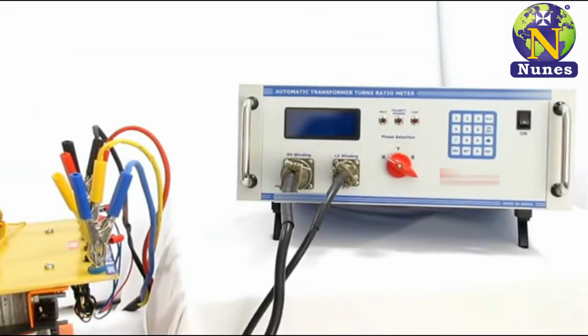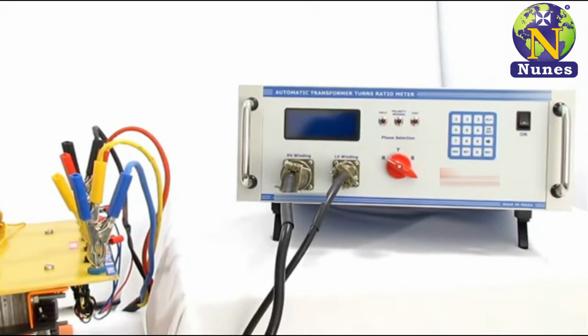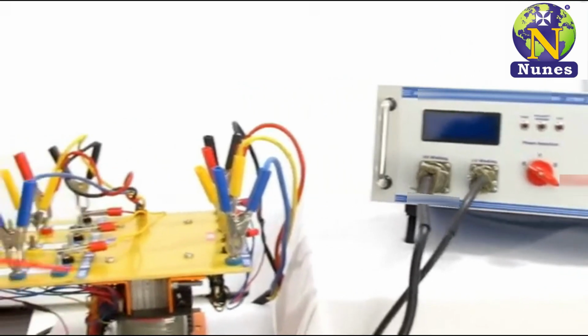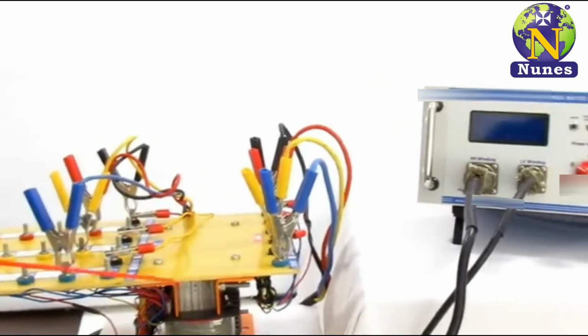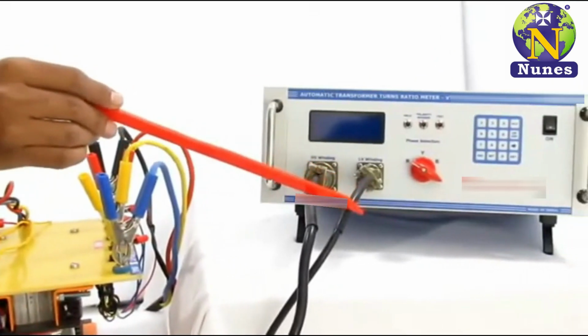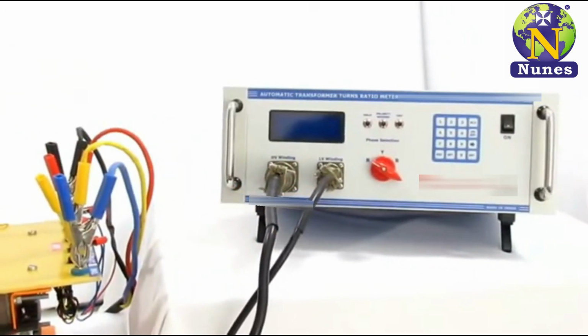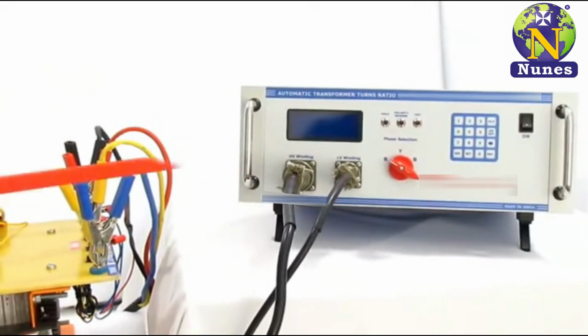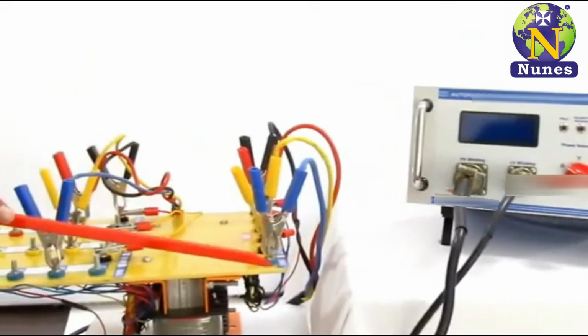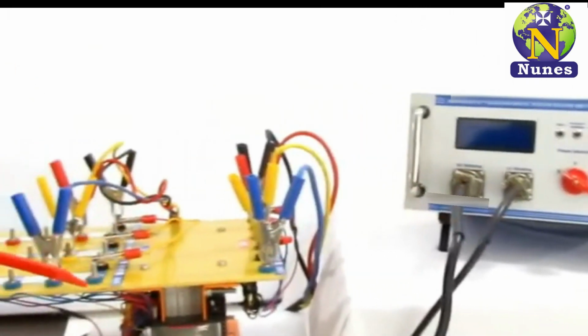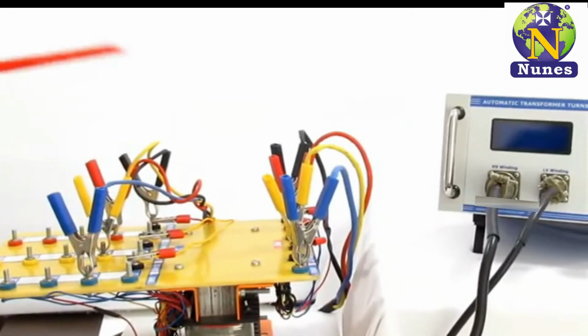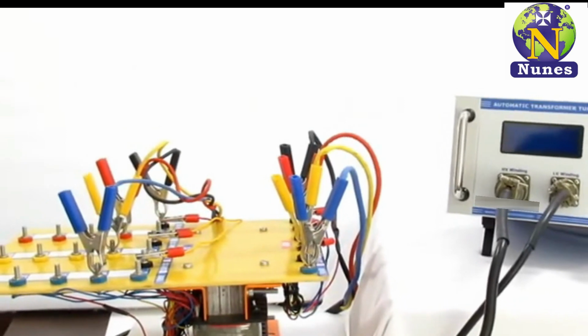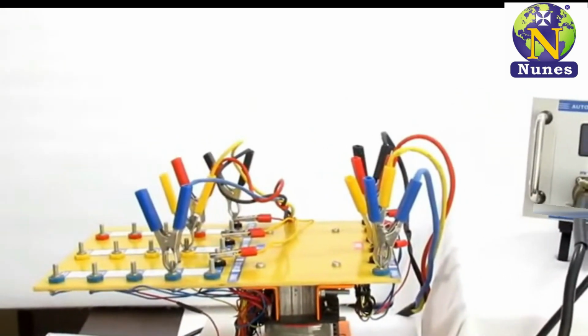Now let us see a live demonstration of ATRM step by step. Do proper connection with the transformer using HV and LV testing cables of ATRM. Connect HV cable to the HV side of the transformer and LV cable to the LV side of the transformer as per color coding of the cable. Don't interchange them. Please verify it.